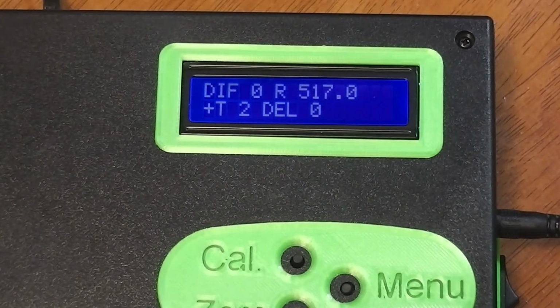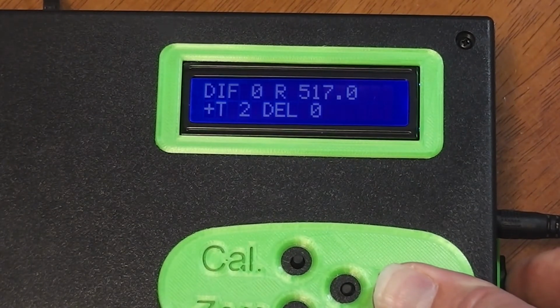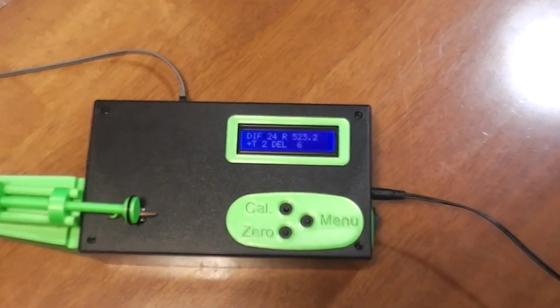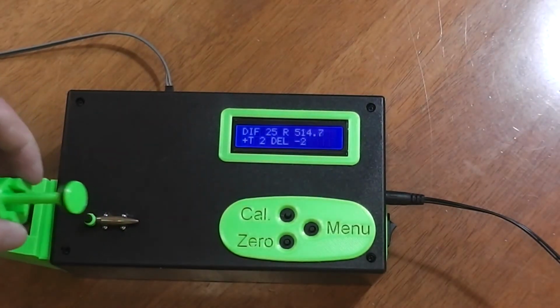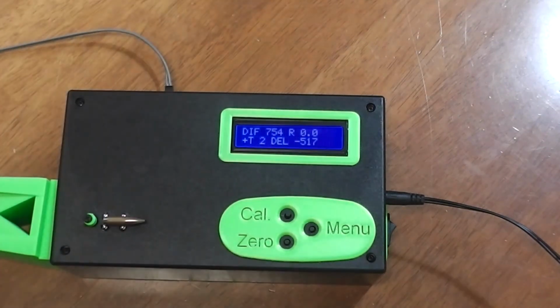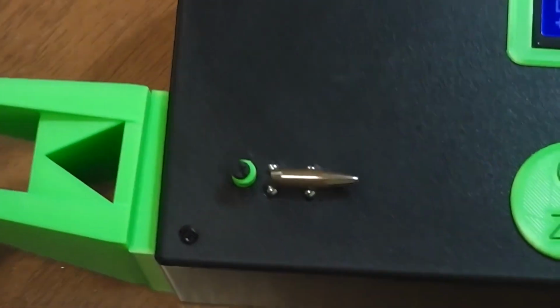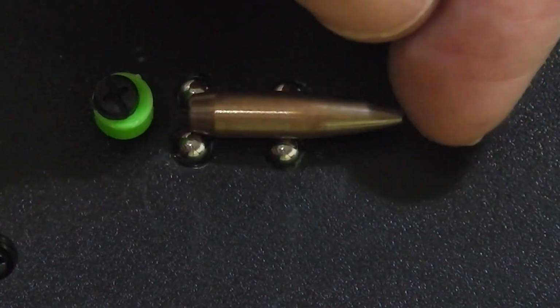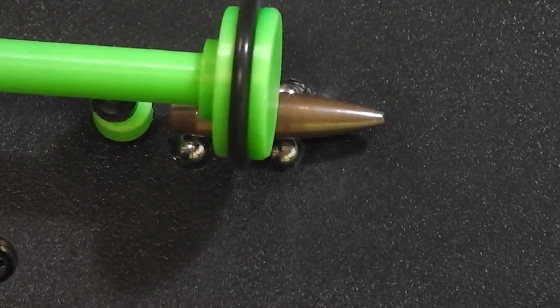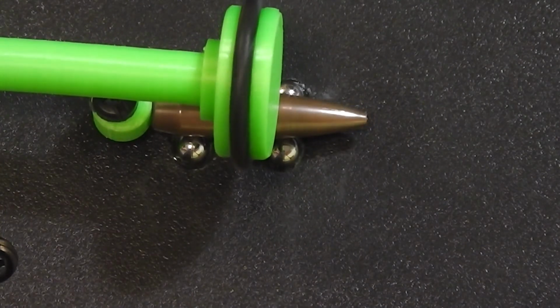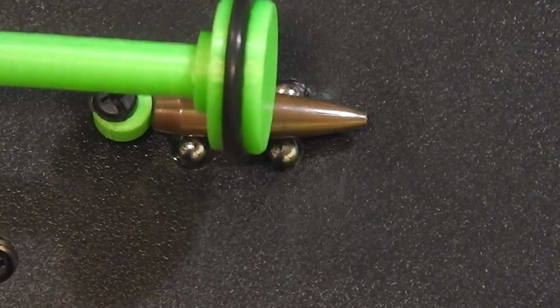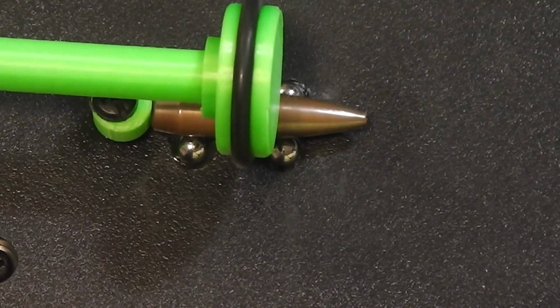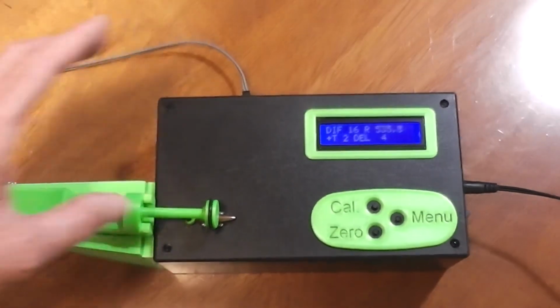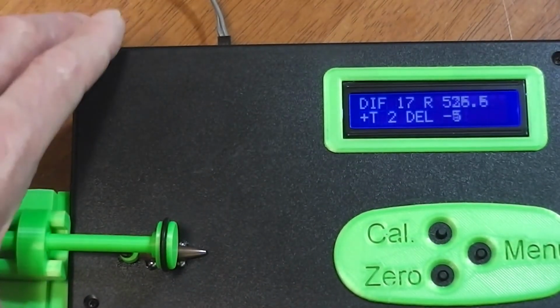So, to actually use it and take some readings, we want to turn the motor on. So I'll just zoom out. Now, the nature of it is that if the projectile is up, and I'll zoom in on this, if the projectile is not seated properly, the motor should actually pull it back to the backstop. And you'll see that. So now you can see that it's right on the backstop. So you can put the projectile down, and then when you're ready, you press 0. Sorry, I will zoom back onto the display. So when the projectile's ready, we press 0 and we watch the difference reading.